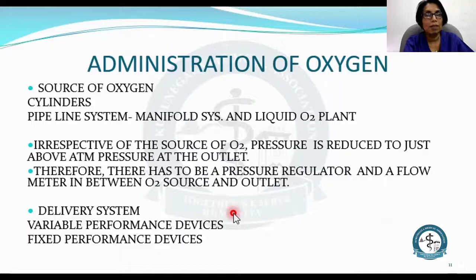Irrespective of the source of oxygen, pressure is reduced to just above the atmospheric pressure at the outlet of the oxygen delivery. Therefore, there has to be a pressure regulator and a flow meter in between the oxygen source and the outlet. When delivery systems are concerned, there are two delivery systems, variable performance devices and fixed performance devices.